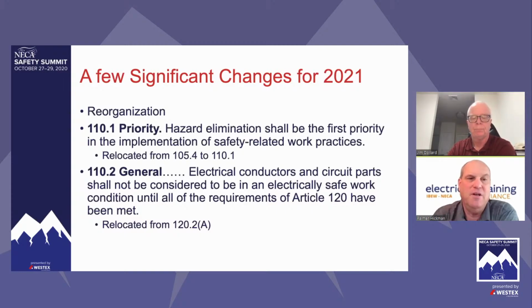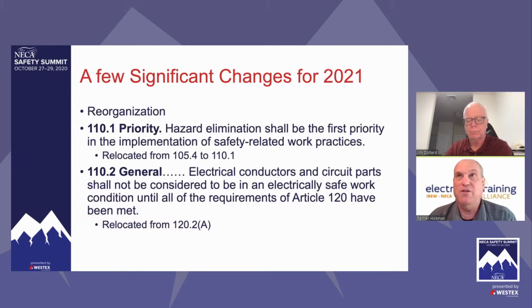So contrary to what you see when you go into 120.5 - and I'll leave that to you to read on your own time - it looks like it is what it says: you've achieved and verified electrically safe work condition when you've done these 8 things. But remember 110.2 in the 2021 edition, remember 120.2a in the 2018 edition - you've got 4 pages of stuff to do in addition to those 8 steps.